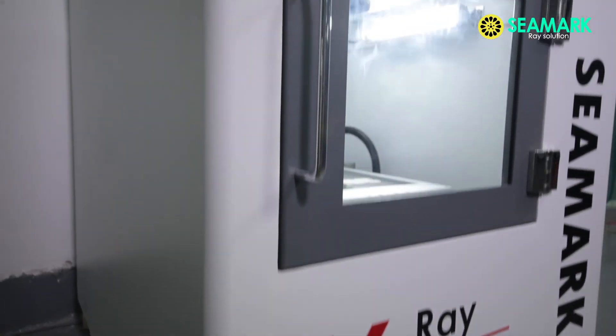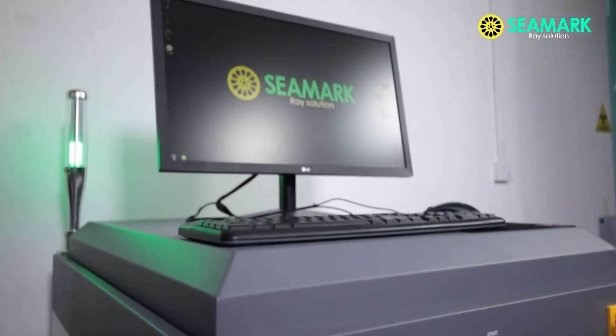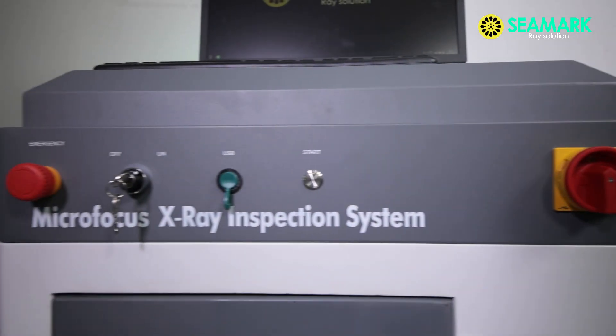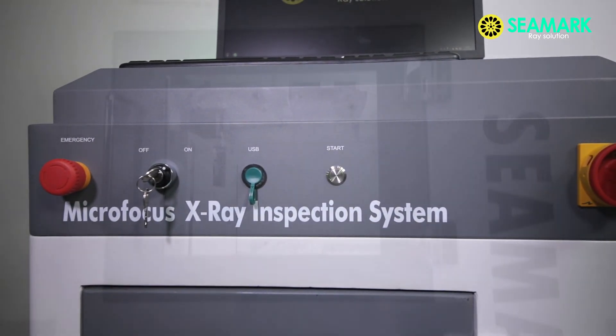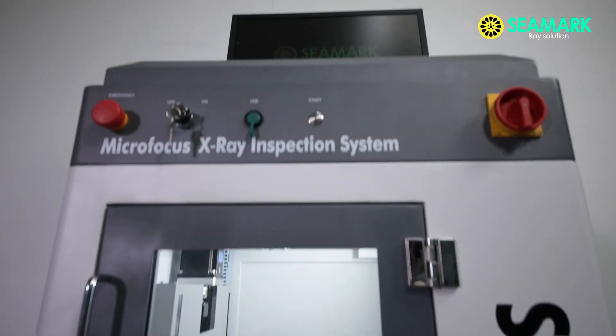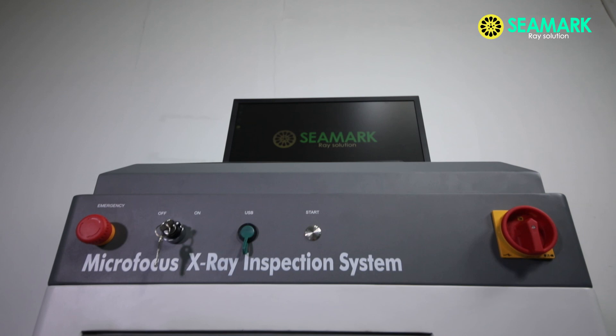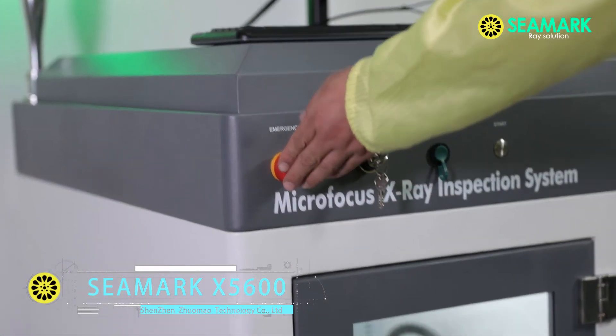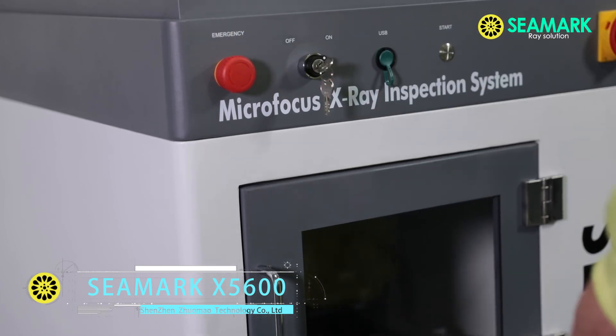We take multiple shielding protection methods for the X-5600. The machine body is wrapped with 5 mm thickness lead sheet, and the window glass is also radiation proof. The machine is equipped with a safety interlock and emergency stop for preventing further damage to the machine.